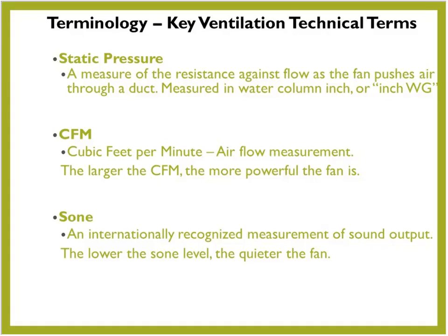Static pressure is one that maybe some of you aren't quite as familiar with. Static pressure is the resistance to airflow. So again, we talked about at the end here, sorry, I had a little interruption there. We're going to talk about installation of ductwork and whatnot, and how that affects the installation and the performance of a piece of ventilation equipment. So we're going to move on to that and how important it is to make sure that we reduce the static pressure as much as possible.